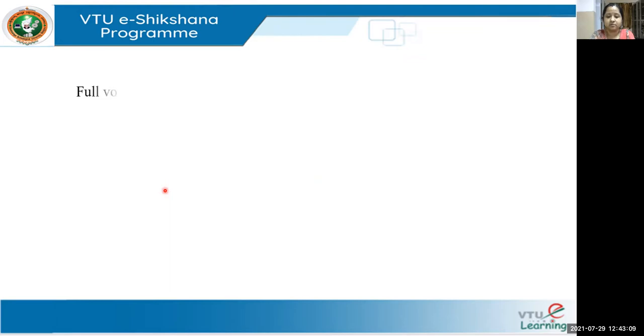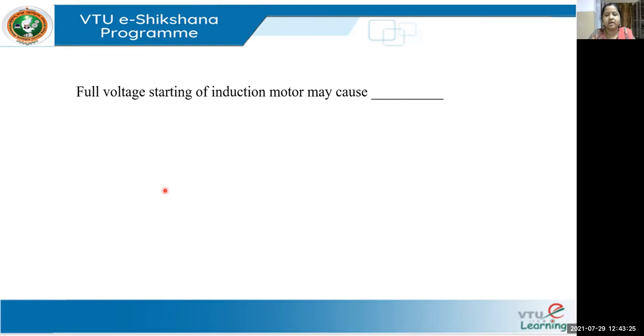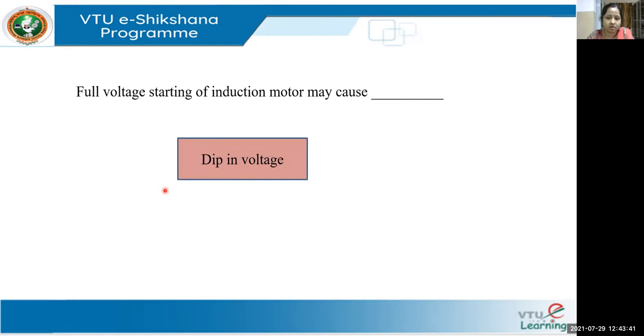Now, quiz time. Question 1: Full voltage starting of an induction motor may cause — what is the first thing you notice? The answer is a dip in voltage. Whenever you turn on your motor at home — like when pumping water — you can see for a second the lights blink: the intensity of the light reduces due to the reduction in voltage. Question 2: While using a stator resistance starter with a three-phase induction motor, the resistance of the starter should be kept at maximum point initially, since resistors are cut out in steps.